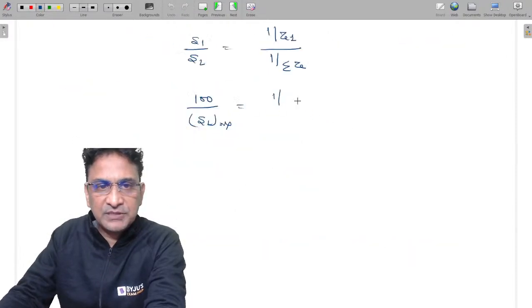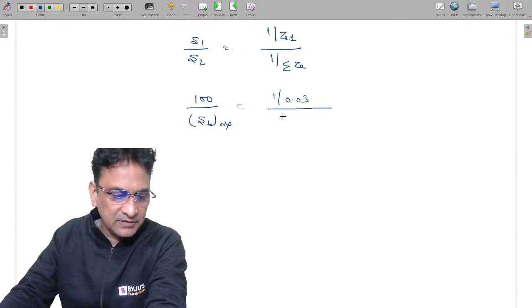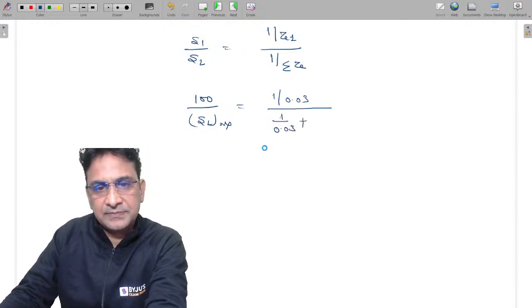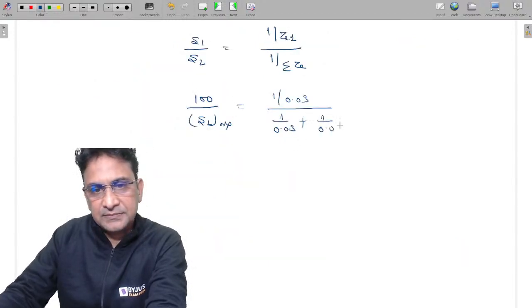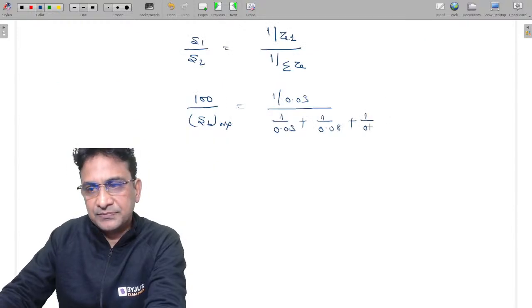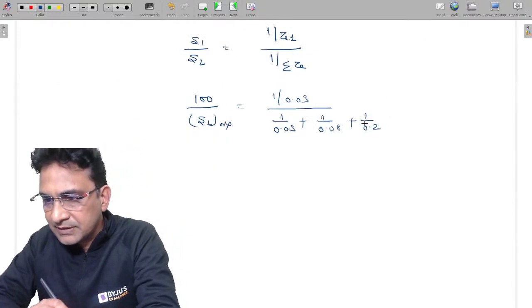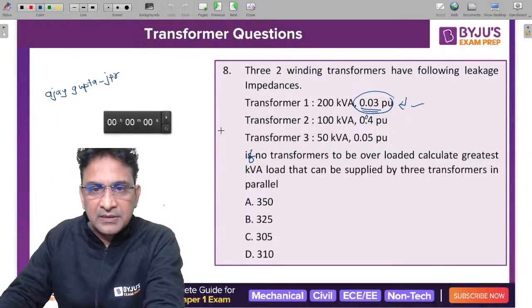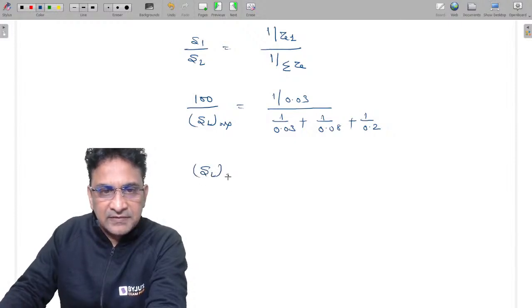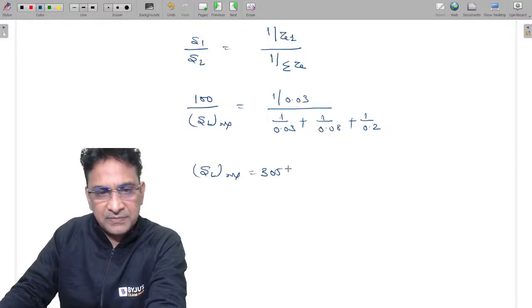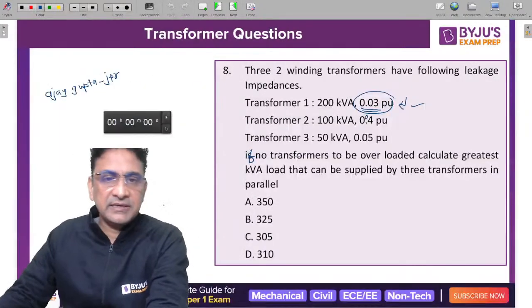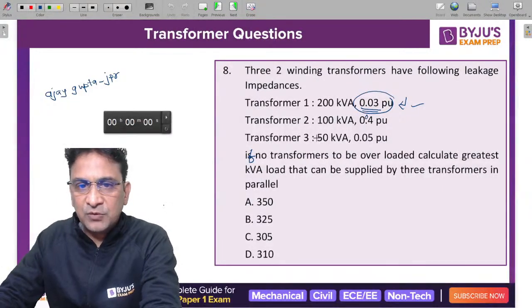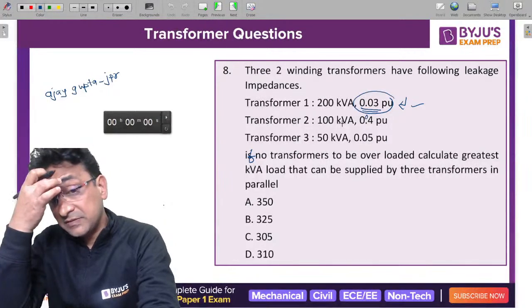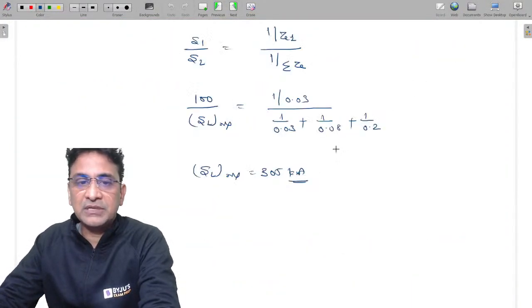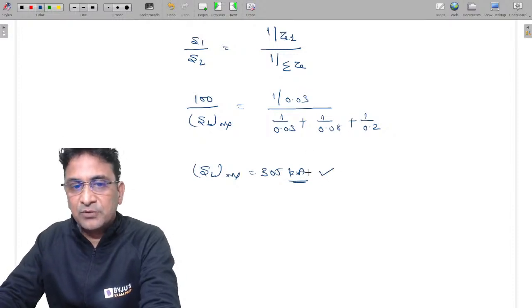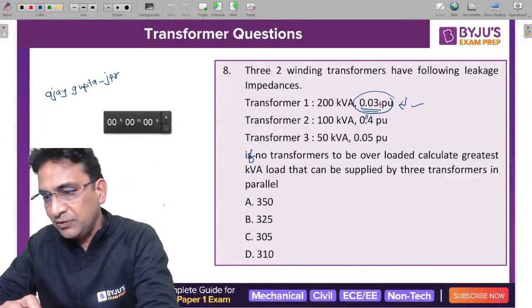ZE1 is equal to 0.03 and the summation of 1 upon ZE is 1 upon 0.03, 1 upon 0.08, 1 upon 0.2. Okay. So if you solve this equation, we will get the value of 305 kVA. So all the parallel transformers combined can give power up to 305 kVA, although their overall rating is 350 kVA, but these transformers cannot supply 350 kVA. They can only supply up to 305 kVA. If you start taking more than this value of power, then transformer 1 will get overloaded. Is it clear?